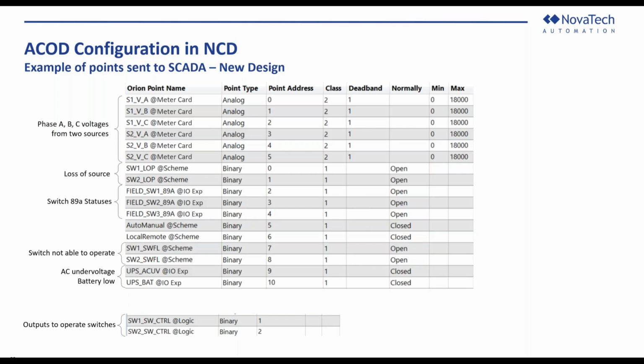If the ACOD is in manual, but it's in supervisory or remote settings, then controls can come from SCADA through the ACOD to the switches so that they can be operated remotely. And down there showing the 2 output controls that we would be using for those.